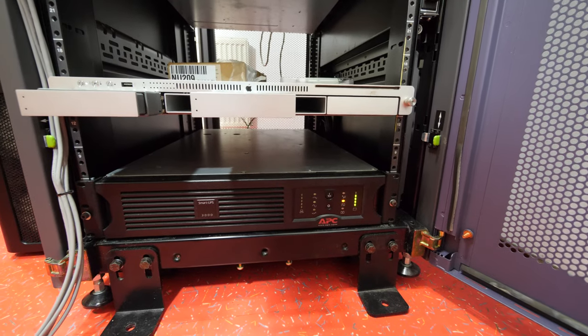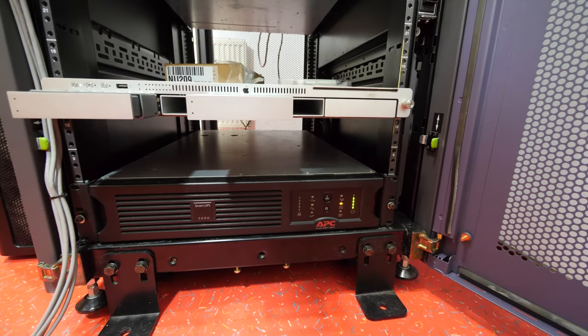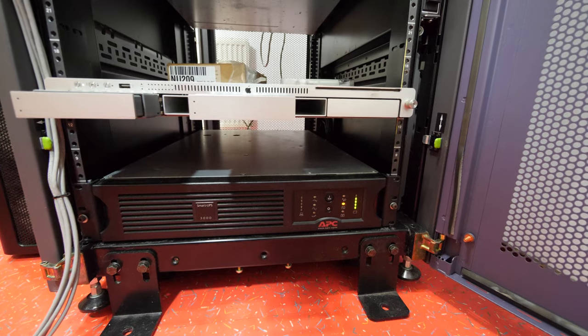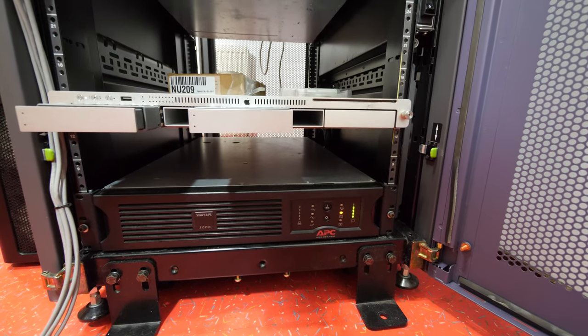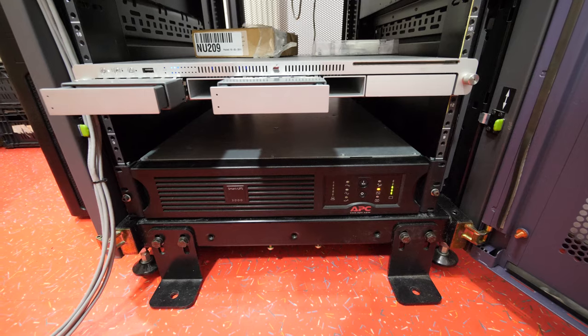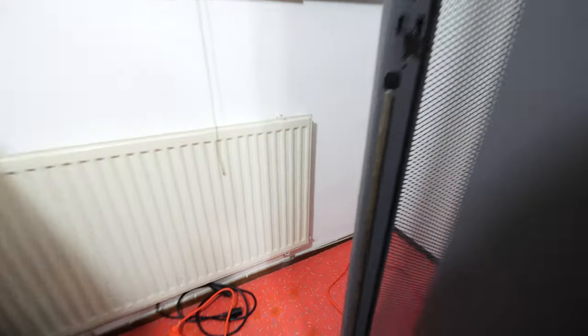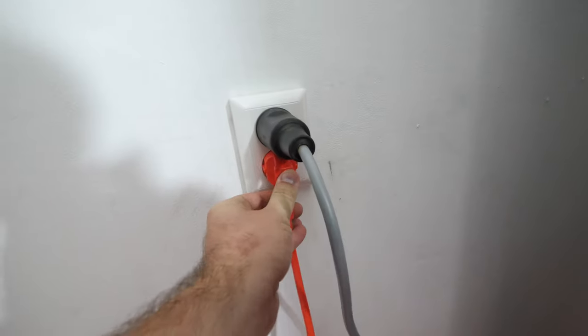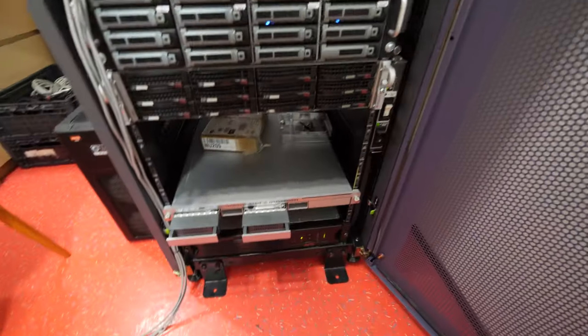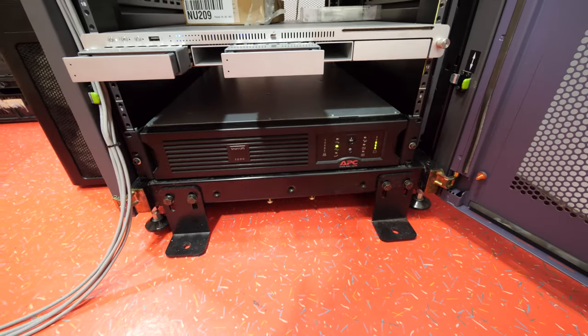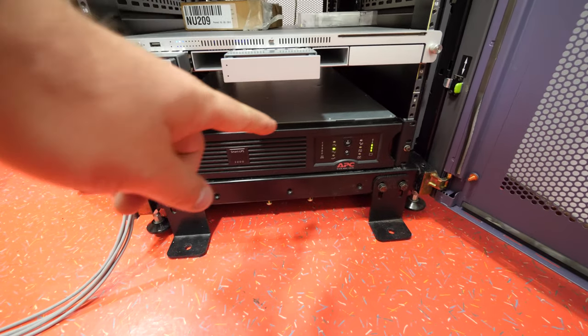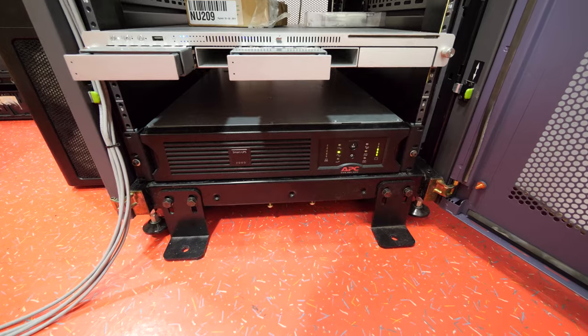Okay, this is how it should work. The beeping and it's still turned on. It's making noise because of the fans and the cooling. The new batteries in the UPS are working, so time to plug in the power cable again. It gives now the status LED that it is on net power.